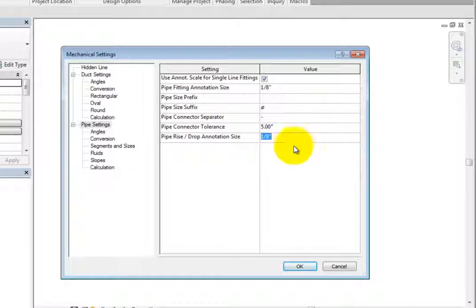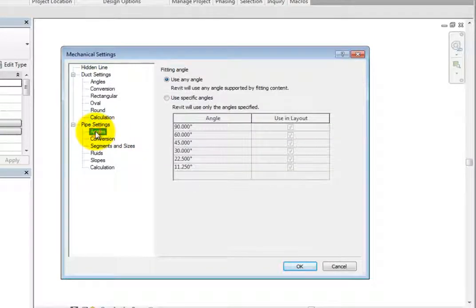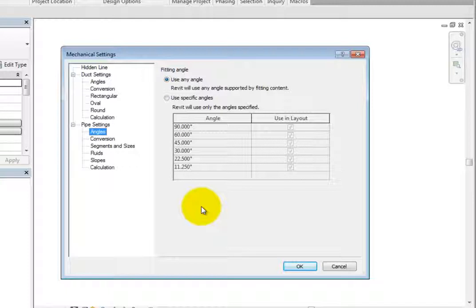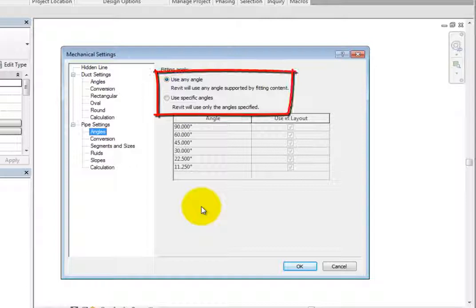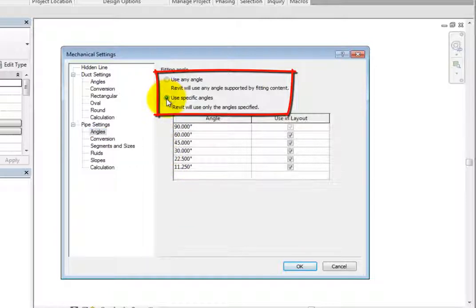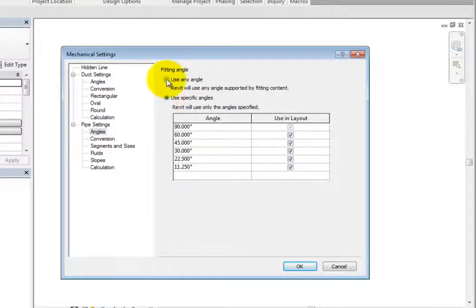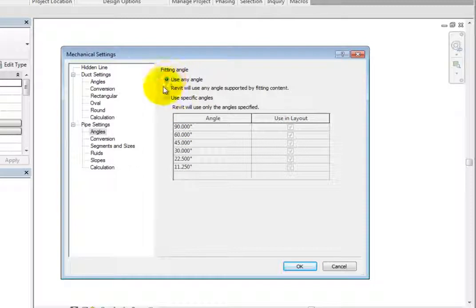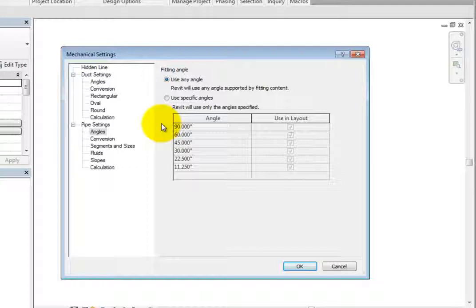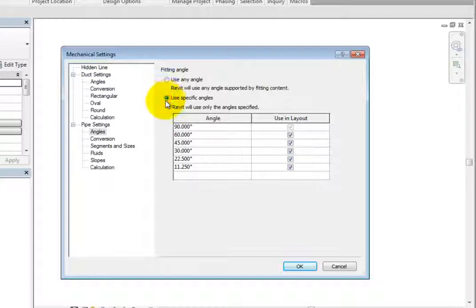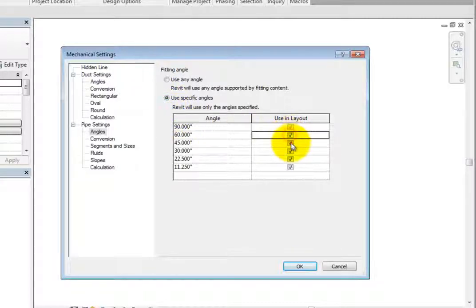Next, select angles. The options here allow you to specify the fitting angle that Revit will use when adding or modifying pipe. Realize that this is not the angles at which pipes can be created. Instead, it is the angles between connected pipes. In other words, the angles of the fittings. You can choose use any angle or use specific angles. With use any angle selected, Revit will use any angle supported by the fittings used for the pipe type. And with use specific angles selected, you can turn on or off the listed angles, but you cannot modify the angles.